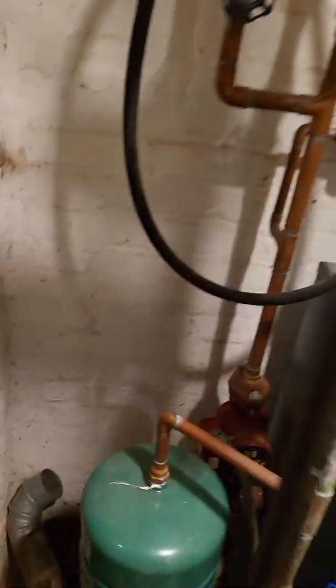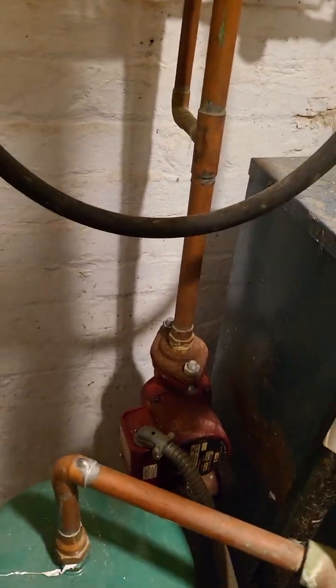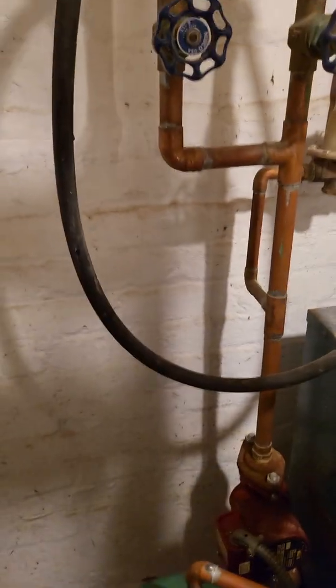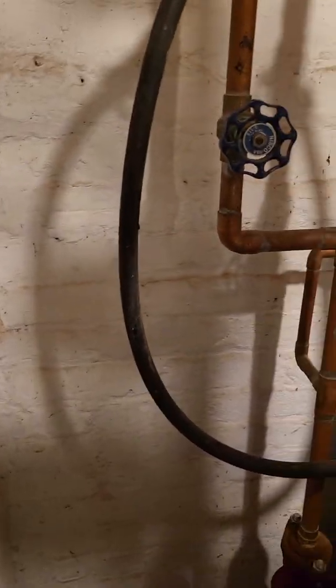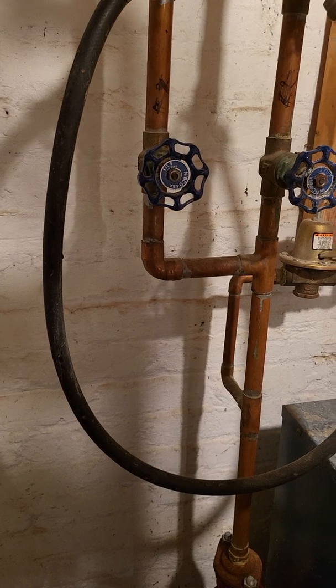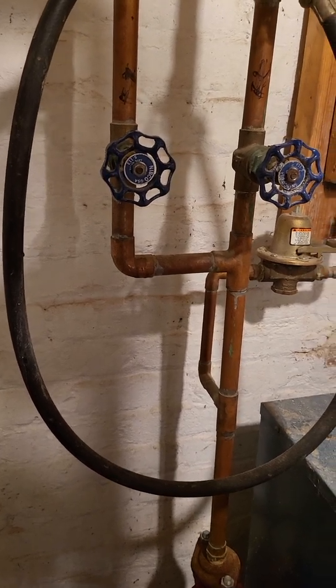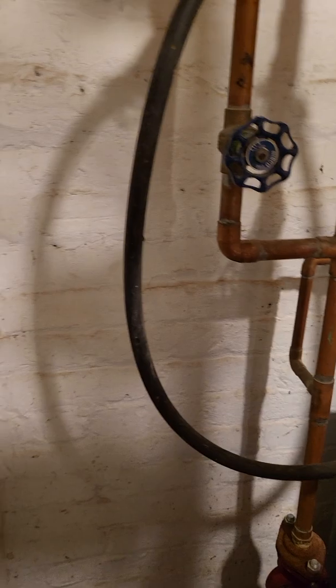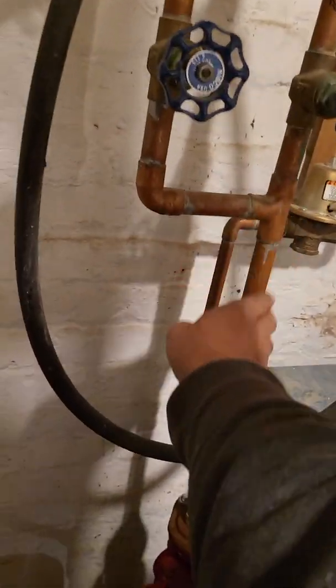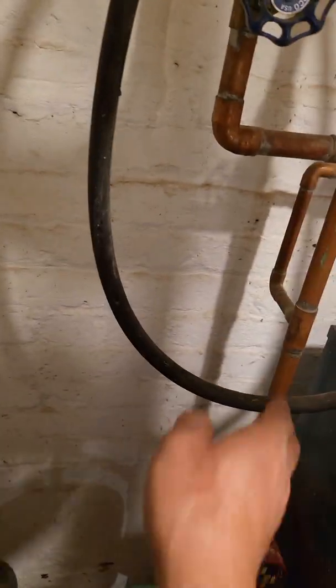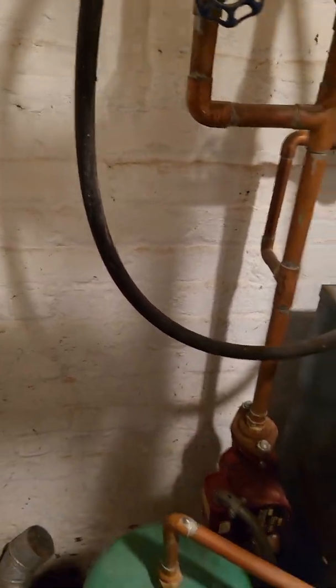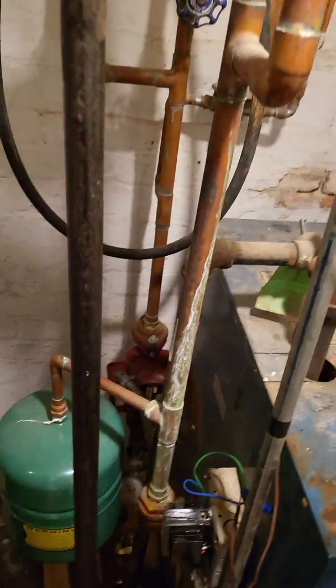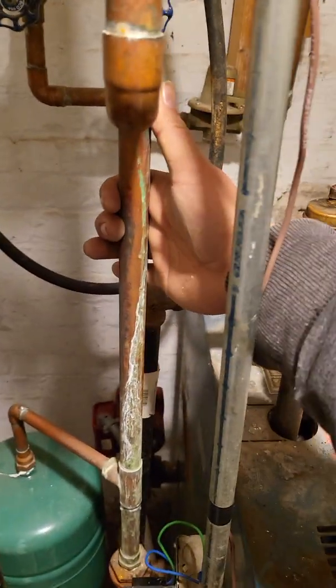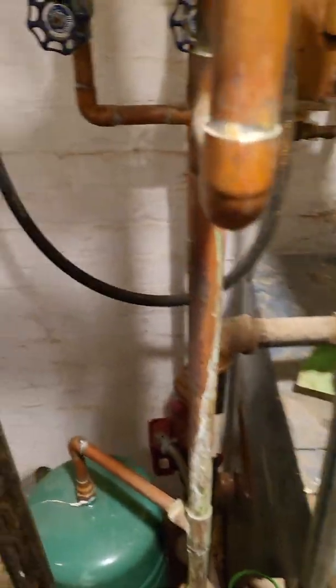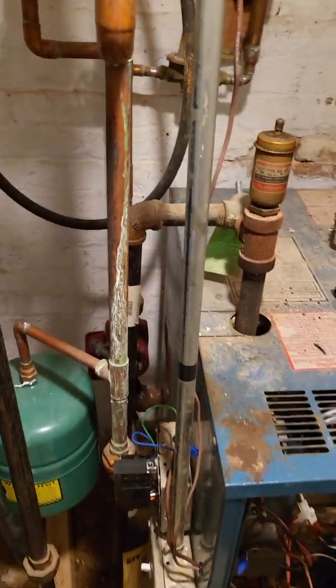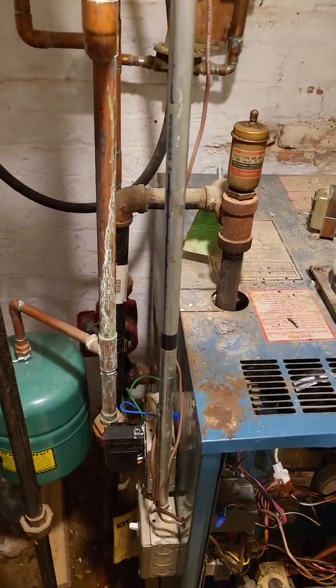This circulator pump here is supposed to circulate the water from here, and the water goes up to the baseboards and comes back here to these two zones, then down to the pump and again inside the boiler and up here. So this pipe is supposed to be hotter than this pipe by at least a 10 degree Fahrenheit differential.